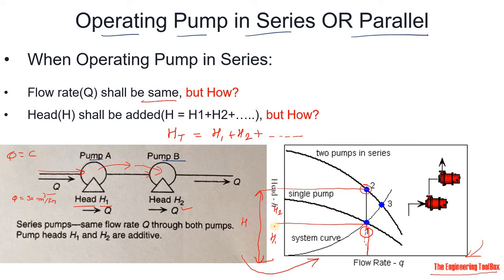H1 plus H2 is the theoretical total head. In a practical scenario, looking at the system curve at point 3, when two pumps run in series the expected head from the pump performance curve should be higher, but practically you get a lower head at that operating point. That is the difference between theoretical and practical performance in a series arrangement.